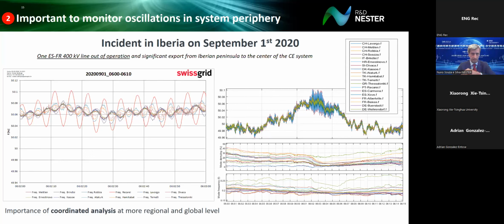You can see in the left side graphic the red line, the one oscillating more, is the Portuguese one, which is the one in Recarei, basically the PMU that we have there, showing a strong oscillation. That is also noticeable in the top right graphic with the blue line, which is also the Portuguese system situation.